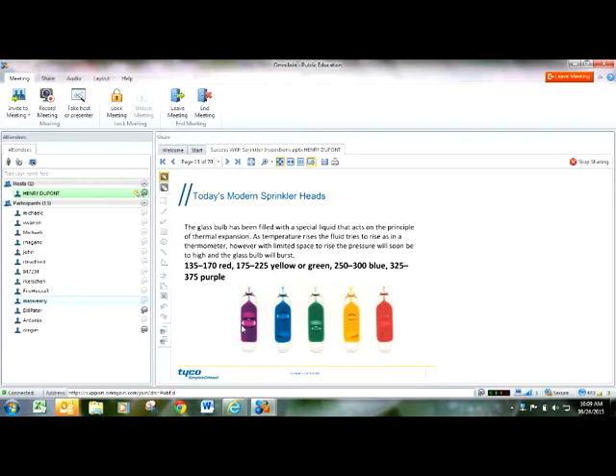Today's modern sprinkler heads are glass bulb sprinkler heads. They work under the same principle as a thermometer. And the bubble in each one of these glass bulbs, as heat rises, the bubble tries to rise, and with a limited space to rise, eventually the bubble will cause the glass bulb to shatter. The different colors represent the different temperatures that the sprinkler head will go off at.